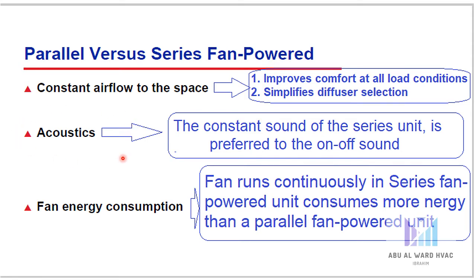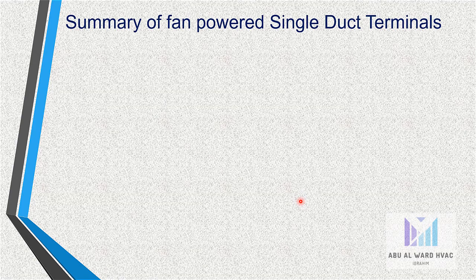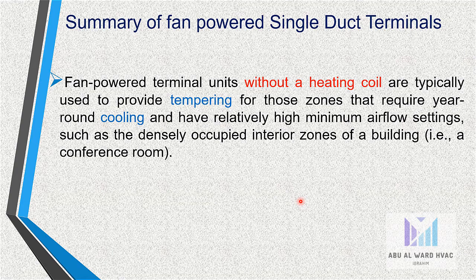The last aspect is fan energy consumption. Because the fan runs continuously whenever the space is occupied, a series fan powered unit consumes more energy than a parallel fan powered unit. The development of high efficiency motors has lessened the energy consumption differences. The fan in a series fan powered unit also costs more than an equivalent parallel fan powered unit because it generally requires a larger terminal fan. Fan powered terminal units without a heating coil are typically used to provide tempering for zones that require year-round cooling and have relatively high minimum airflow settings, such as densely occupied interior zones of a building — for example, a conference room.